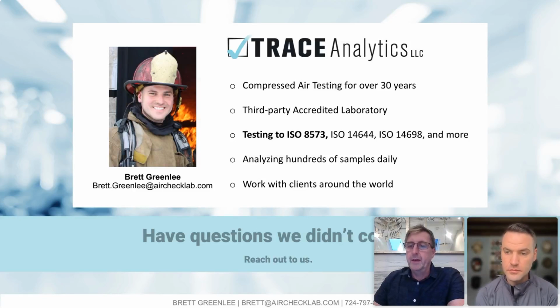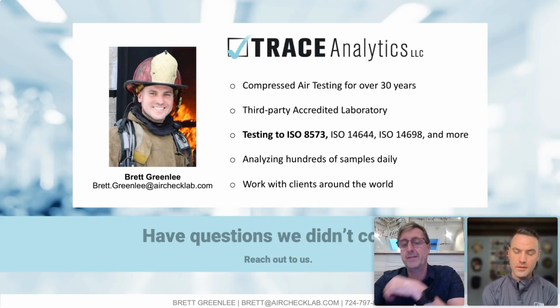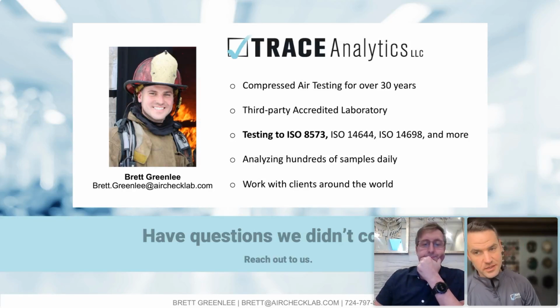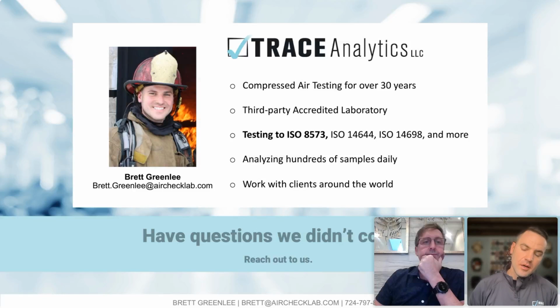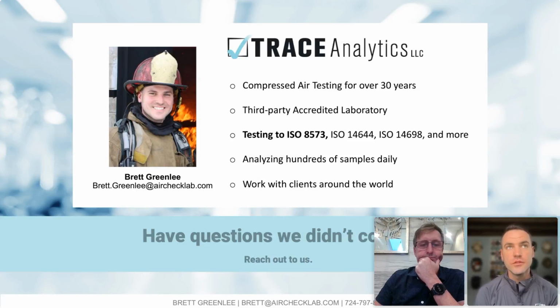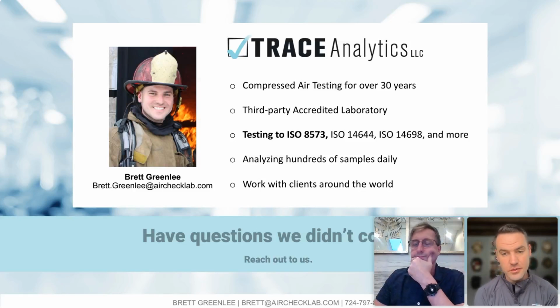Question from Timothy. How did we arrive at the targets for various applications? Are they universal or based on localized risk assessment? So I can't speak to the BCAS. I think he's talking about purity class limits. I think for BCAS they recommend a 1-2-1. I don't know how they came to that, but they used to actually have it different. Direct contact was 1-2-1, and indirect contact I think was 2-4-2 or something like that. But now they've changed it so that both direct contact and indirect contact are 1-2-1. So speaking to the BCAS, I don't know how they came to those limits.